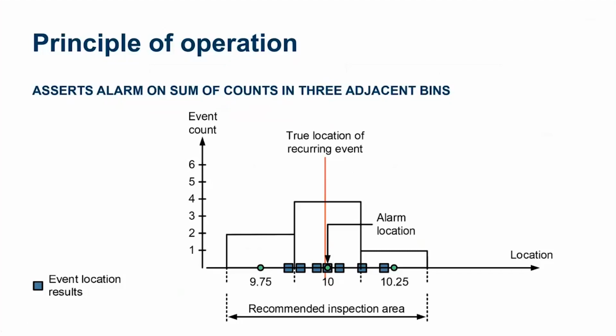With that, do we have any questions, Reagan? Yes, Jared. Which SEL relays have traveling wave fault location? Yeah, it's going to be the 411L. That's going to have our double-ended traveling wave fault location, so that's going to require fiber optic communications between the two. And then the T400L and the T401L also have traveling wave fault location. That can be single-ended or double-ended.